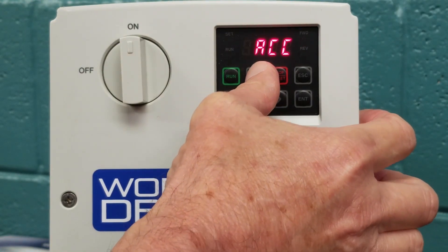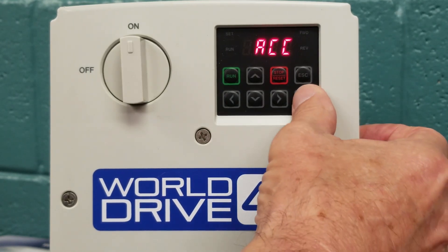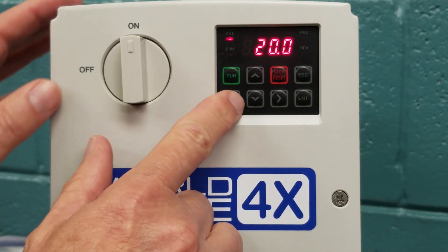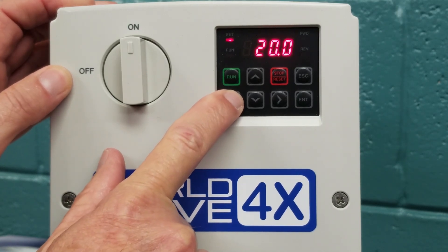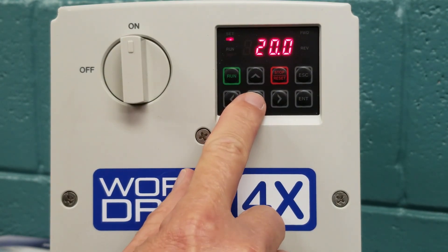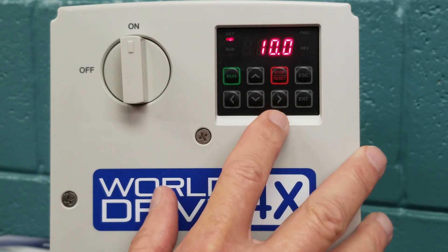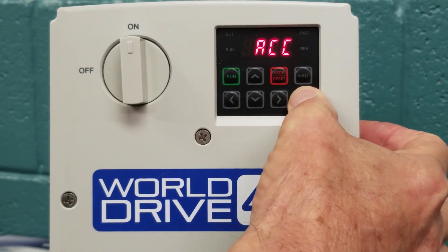We are going to press the up button, and you will see ACC, which stands for acceleration time. We hit the enter key, which allows us to go into the acceleration parameter, and we can see the factory default is at 20 seconds. For this illustration, we are going to change the 20 seconds to 10 seconds. You can use both the left and right arrow keys to scroll back and forth to make your appropriate changes. We hit enter twice to save the parameters.